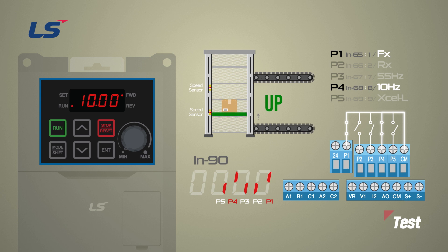In the lift load test of multi-stage control: ascending operation runs in the forward direction and descending operation runs as a reverse signal. The speed is 55 Hz for multi-step first stage and 10 Hz for multi-step second stage. When ascending, it uses general acceleration and deceleration from the operation group ACC-DEC. When descending, it is set to operate in single-stage multi-stage acceleration and deceleration.